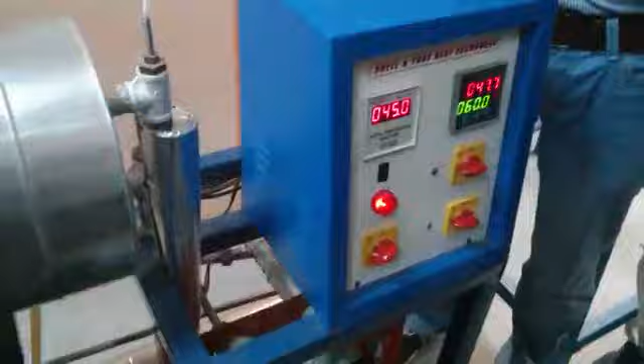The flow rate varies from 25, 50, 75, 100, 125. These values will be mentioned in the question paper itself. For example, they'll ask you to set the hot water temperature as 70 degrees centigrade, keep the hot water flow rate at 200 liters per hour, and vary the cold water flow rate as 50, 75, 100, 125. That means you have to take 4 sets of readings.